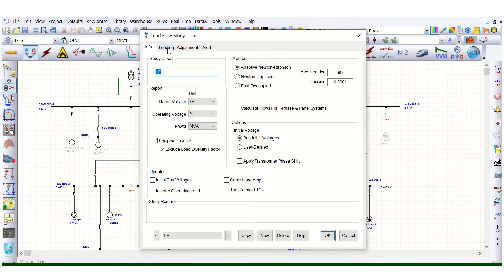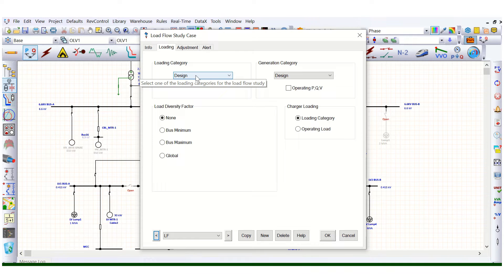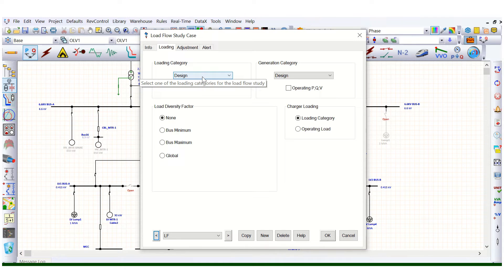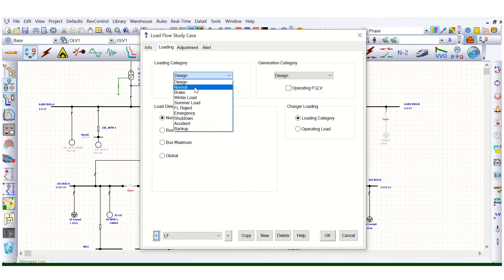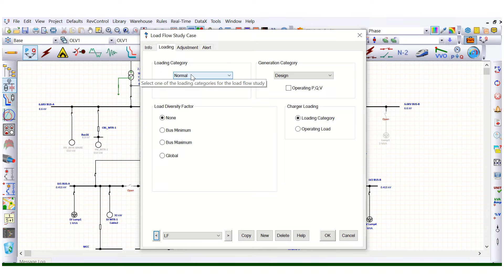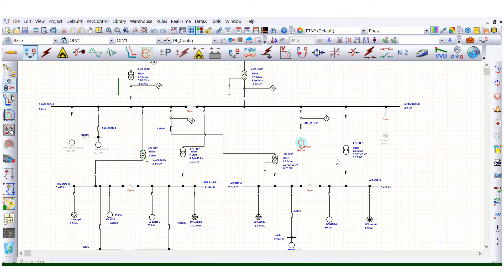Under this study case editor, we can assign whether it is normal or design. If it is selected as design, that means we are simulating this load flow analysis considering 100 percent load, that means the rated connected load. That will be the maximum rated connected load, but that will not reflect the real scenario. So in that case we need to select the normal option, which means 80 percent, 85 percent, or 90 percent. Here we are not defining any load diversity factor.